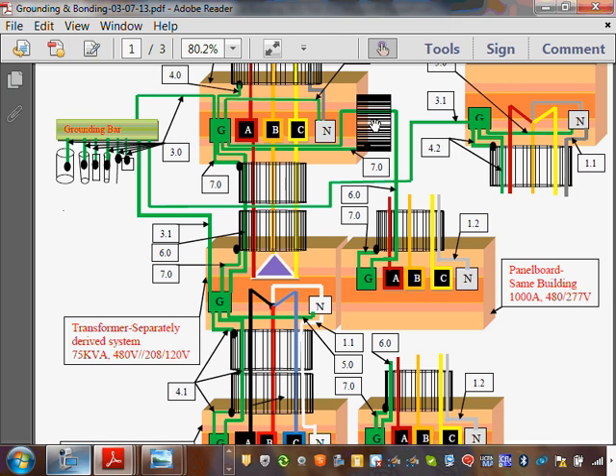Most of the time, guys, if you are to bond, the same conductor, 6.0, come over here, bond this conduit here, move in with the bonding bushing, bond this conduit, the same conductor, loop it, bond this conduit, and come to the ground. So you can use one conductor to bond the conduits at both ends and go to the panel. Any questions about 6.0 or 7.0?